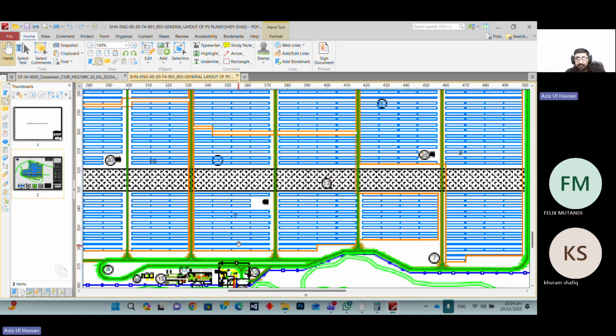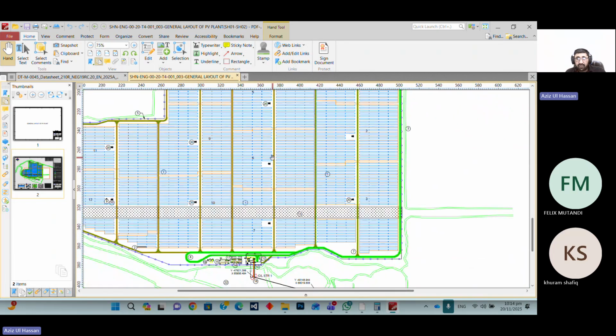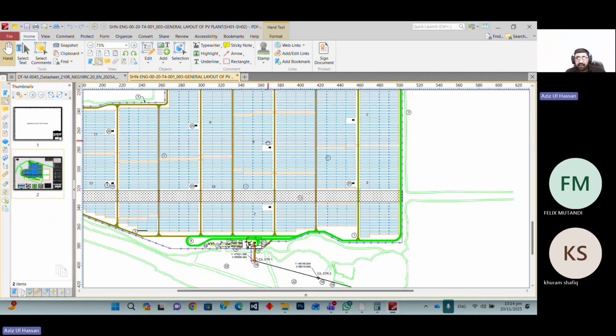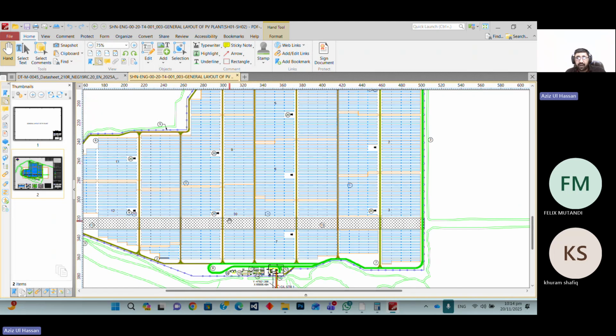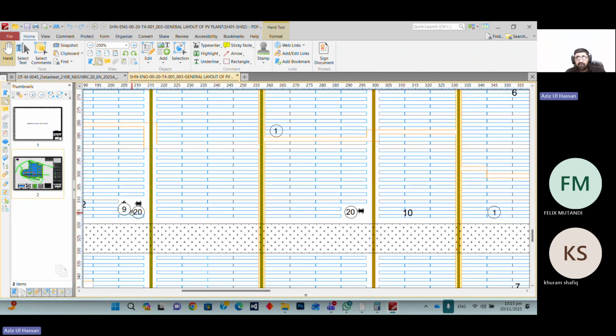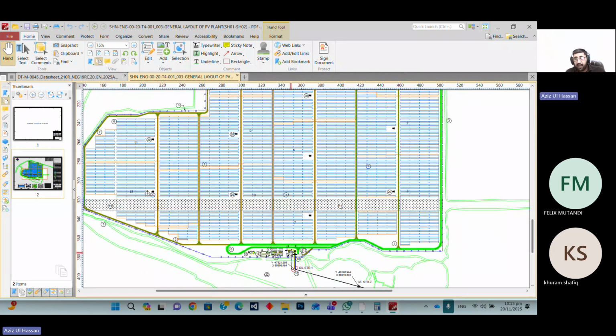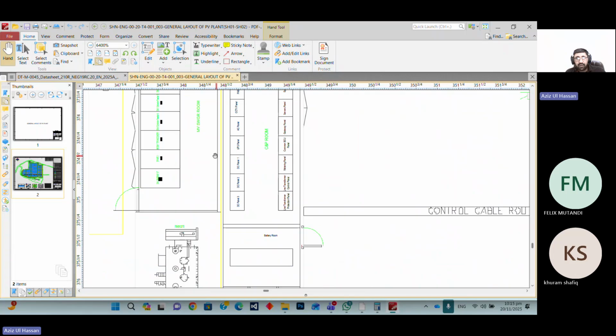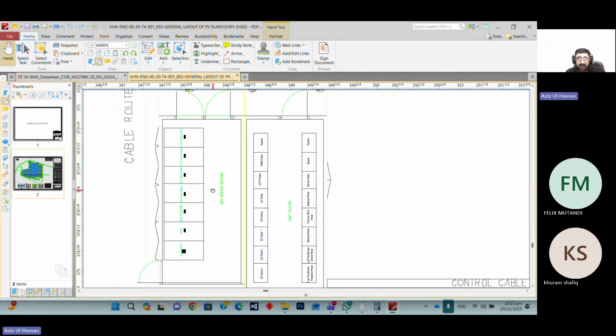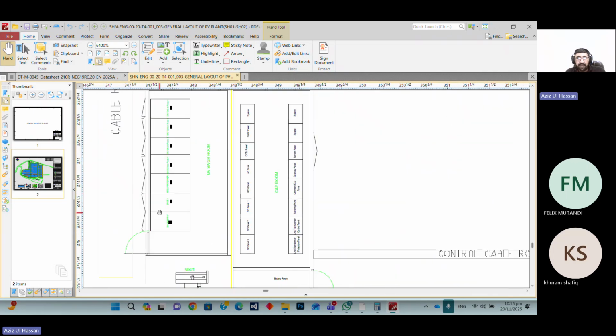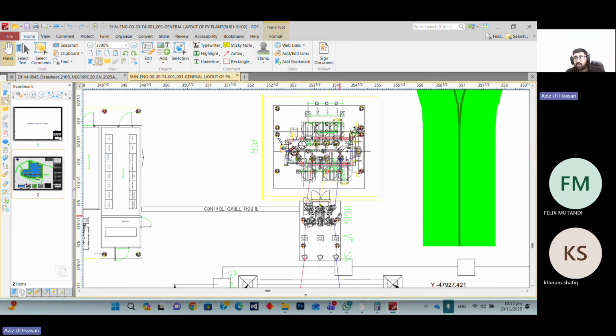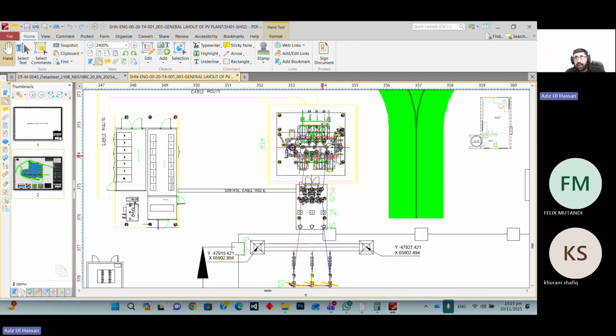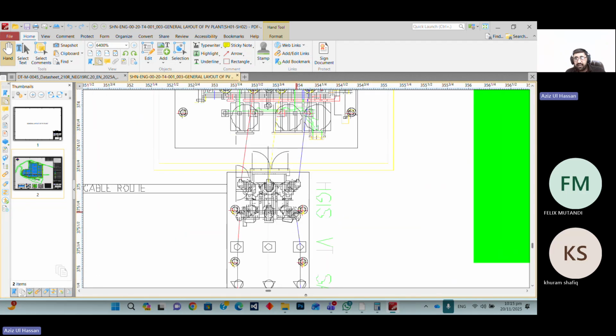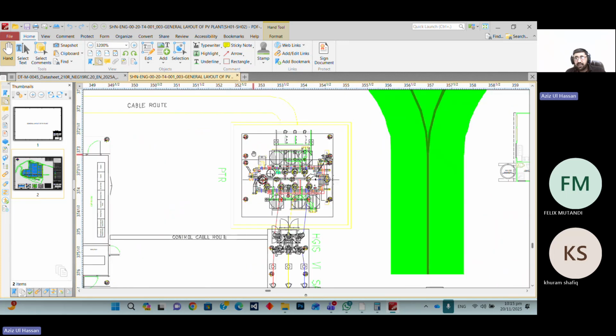Now we connect 4 to 5, 4 to 6, and 5 to 6, and then we run the cable. Similarly, we connect 9 to 10, 10 to 7, and 7 to the others, and then we make 11 to 12. So we have made 4 feeders available, and we connect them in our switchgear rooms. You have seen that these panels are available. From them they make an output panel, they connect with each other, and they connect through to the transformer. This is the HV transformer, 33 to 66 kV.